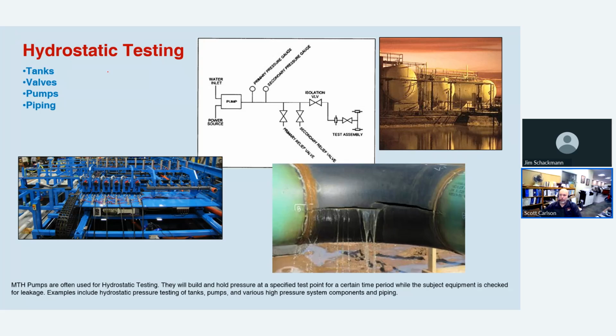Next on our list of applications is hydrostatic testing. With hydrostatic testing, any manufacturer that makes any kind of a tank, piping, or any other piece of equipment that is going to be put under pressure, one of the easiest ways to test it while it's still in the manufacturing process is to hydrostatic test it using a regenerative turbine pump. With the regenerative turbine pump, you can use your pressure gauges to decide what pressure you're going to test it at.